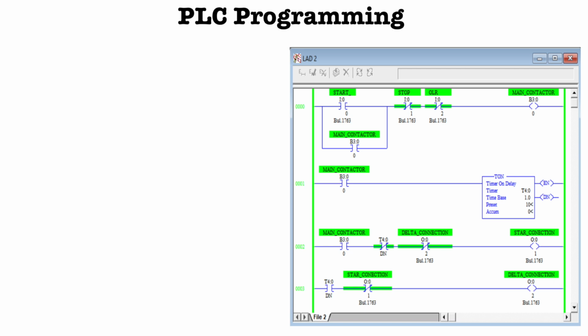In the third rung, you can see the main contactor is connected to the star connection, and in this rung you can see the two NC switches, meaning two interconnections are provided. One is for the timer done bit, that is T4 colon 0/done bit, and one for the delta connection in the form of an NC switch, normally closed switch, right? And you can see in the last rung the done bit of the timer is connected with the delta connection, and in this rung also one interconnection of the star connection is provided. As you can see in the diagram, the NC switch of the star connection is also connected in the fourth rung, right?